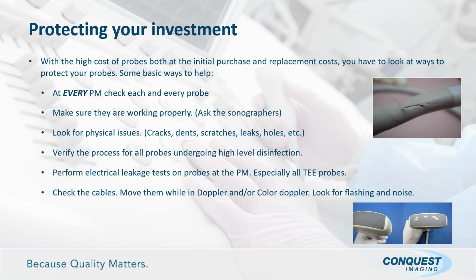Make sure that any probes going through high-level disinfection are being disinfected properly, and especially TEEs, that you don't have bite marks and you're not flooding the probe. You really need to do an electrical leakage test on your probes at every PM. TEE probes are supposed to be done after every patient now. It's a requirement. And they really should be done even on the PMs. And check your cables again. Move it around, put it in Doppler or color Doppler and see if you get any flashing and so forth.